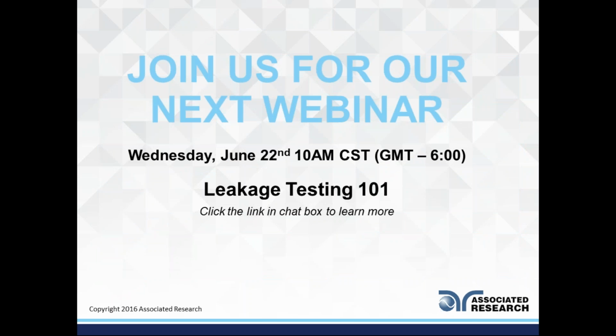This is the first part of a two-part series where we'll talk about all those fault conditions, from open ground to open neutral, reverse polarity, what they mean, how our testers do that, and if you're properly testing, if you have an applied part on your medical device, if you need to do applied part to applied part hipot. That's something very discreet that a lot of people, if you have an applied part, should be doing, but not many know about it.